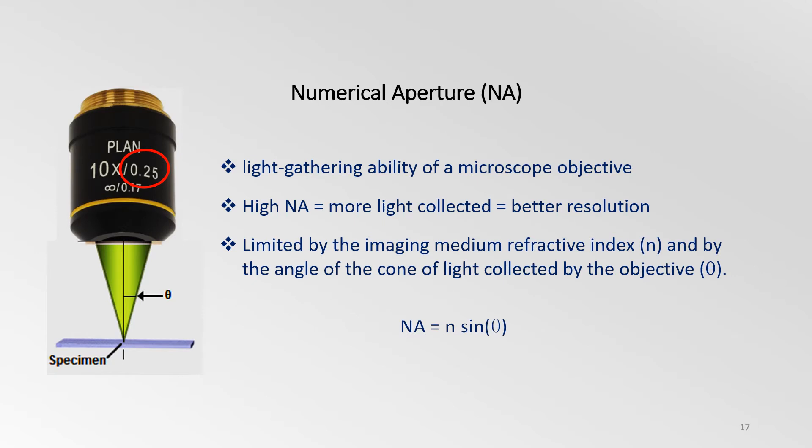As I mentioned earlier, the numerical aperture characterizes the range of angles over which the objective can accept or emit light. The light-gathering capacity of an objective directly influences its ability to resolve fine specimen detail. NA is given by the simple expression N sin theta. N represents the refractive index of the medium between the objective front lens and the specimen, and theta is one half of the angle of light collected by the objective.